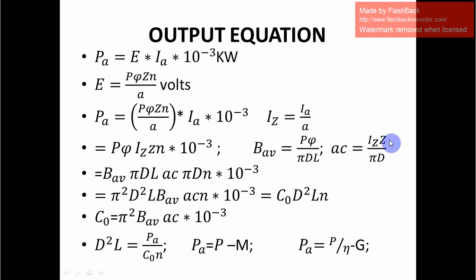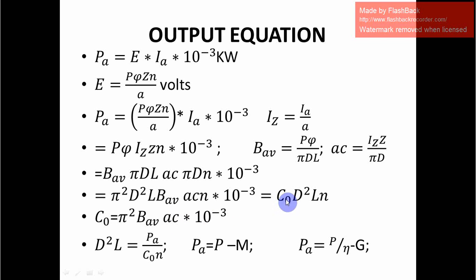After substitution, P·φ equals B_av·π·D·L and I_Z·Z equals AC·π·D. Multiplying these together with n times 10 to the power minus 3 gives π²·D²·L·B_av·AC·n times 10 to the power minus 3. We replace the term π²·B_av·AC times 10 to the power minus 3 with C₀, where C₀ is the output coefficient.